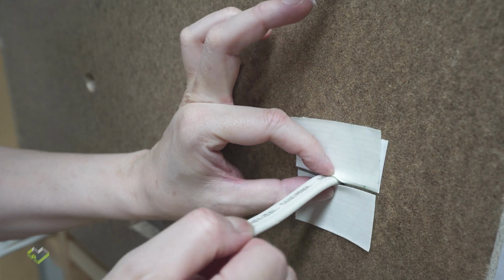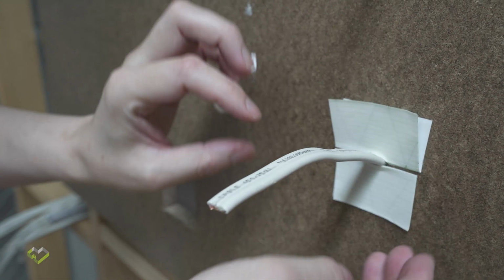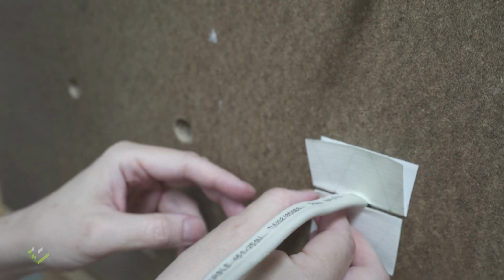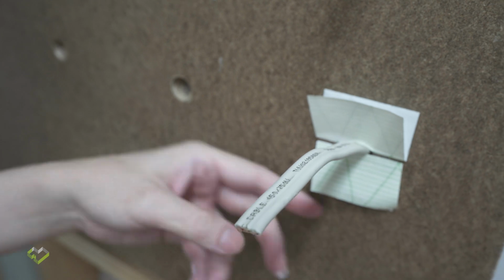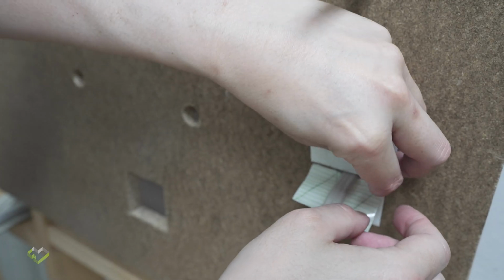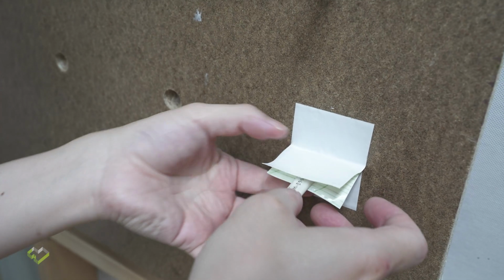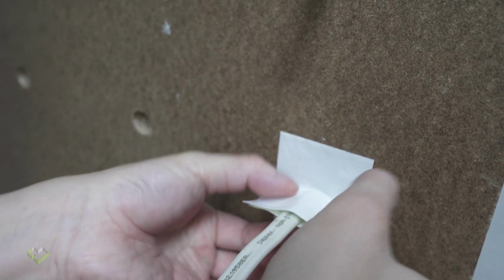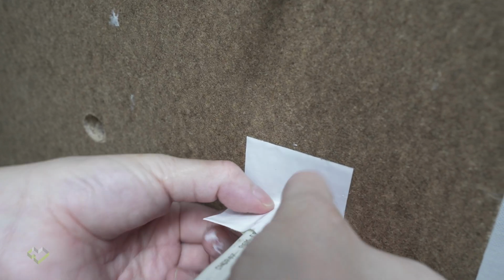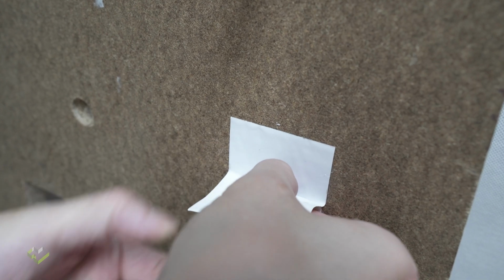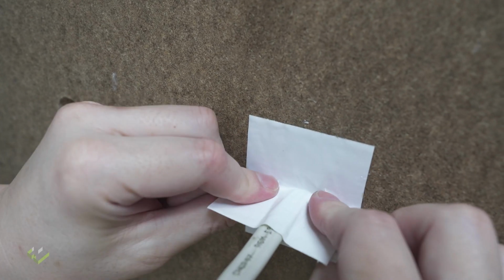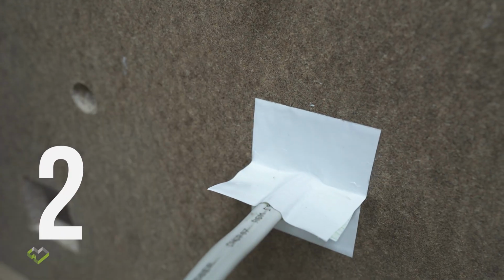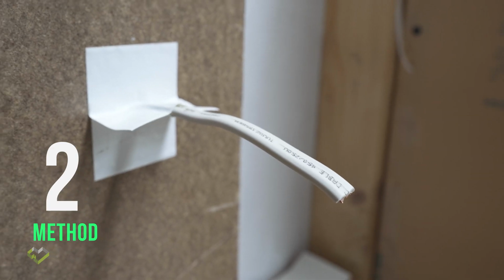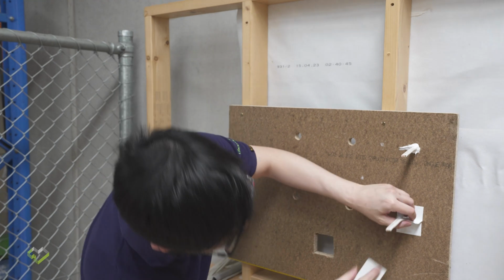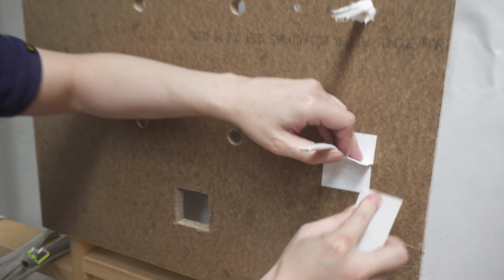Then we can pull it across, get to the right length that we need, peel off the release liner, fix half of it so it's holding the cable in place, and then we can push it down a bit, peel off the other half, and then we can tightly squeeze them together, and then from the wall side, pull it back out. So if there's any air bubble, we squeeze it out. Looks pretty good. After we squeeze the tape together, we use a plastic spatula to work to the edge, to the corner, to make sure it's tightly fit.